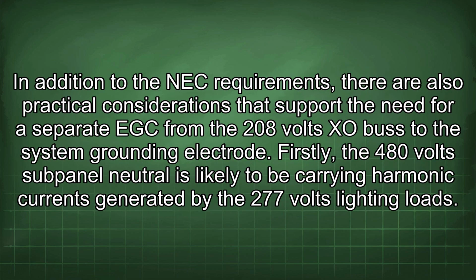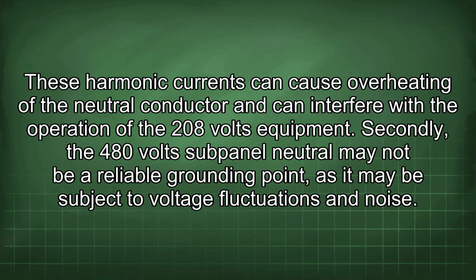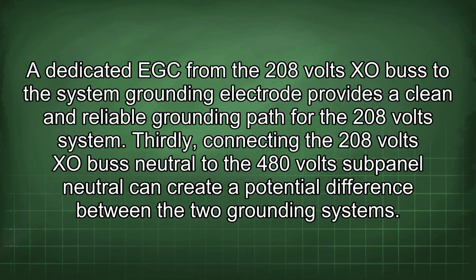In addition to the NEC requirements, there are also practical considerations that support the need for a separate EGC from the 208 volts XO bus to the system grounding electrode. Firstly, the 480 volt subpanel neutral is likely to be carrying harmonic currents generated by the 277 volts lighting loads. These harmonic currents can cause overheating of the neutral conductor and can interfere with the operation of the 208 volts equipment. Secondly, the 480 volt subpanel neutral may not be a reliable grounding point, as it may be subject to voltage fluctuations and noise. A dedicated EGC from the 208 volts XO bus to the system grounding electrode provides a clean and reliable grounding path for the 208 volts system.